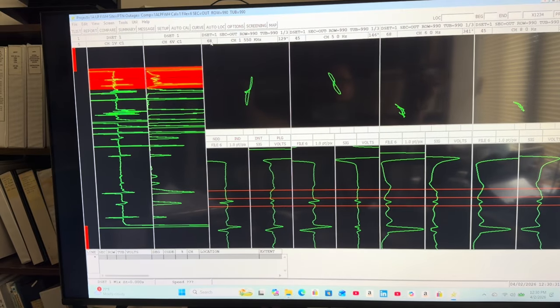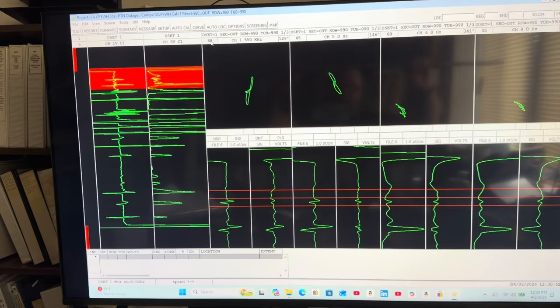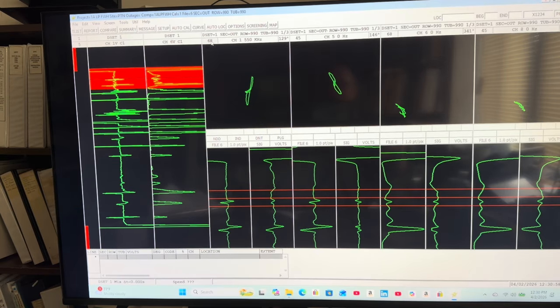So once again, you're not going to see anything like this in an ASME tube because you just have flat bottom holes and some grooves. And then if you have a calibration standard for doing array, you might have a spiral groove in it to make sure your probe's wired directly and your configuration's correct and all your channels are firing in the right order. But again, perfect calibration tubes like that are meant to calibrate your system and to periodically check your system, make sure that it hasn't drifted and that everything's still operating correctly. But those simple signals will not really teach you how to do data analysis.